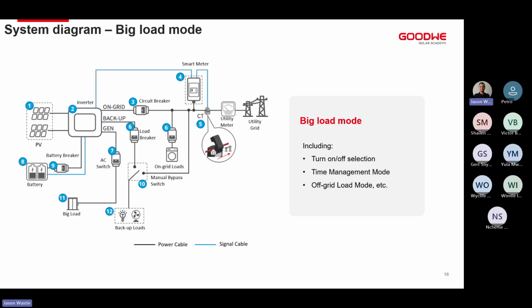Next is the big load mode or secondary AC output. This is where we use the generator port as a secondary AC output. This is where we would put bigger loads on, or critical loads of less importance, or loads that we only want to run on the backup side of things during certain conditions. We can have it as a manual start-stop, and this is where we would use our second contactor or dry contact relay built into the inverter, and we can have everything start-stop dependent on what we want to do. So we can manually turn it on or off, allowing both backup port and generator port to run towards loads all the time.